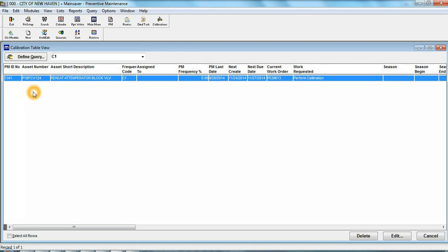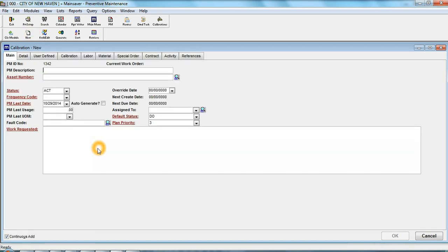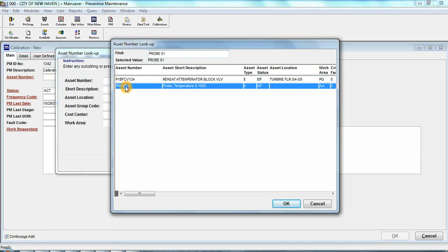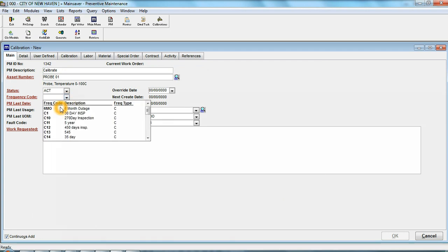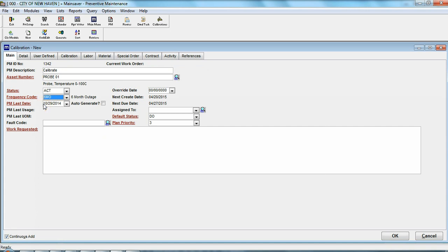So now what we have to do is set up a calibration. It's essentially a PM record, and this controls when this is scheduled. So this is just to calibrate. And the asset, I'm going to look up my temp probe. So I've got probe 1. And I'm going to do this every 6 months. And let's just say the last time we did it was 6 months ago. So it was due on 10/26. And I'm just going to say perform calibration on attached sheet, because we'll get the work order page and we'll get a page with the calibration specification.